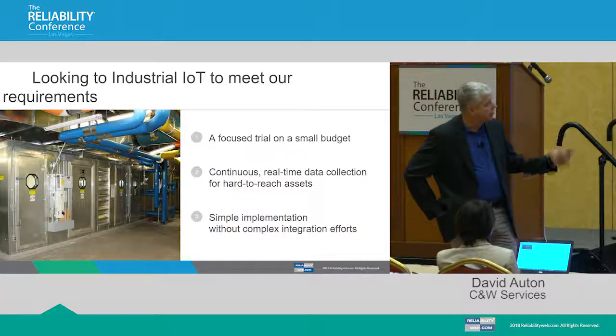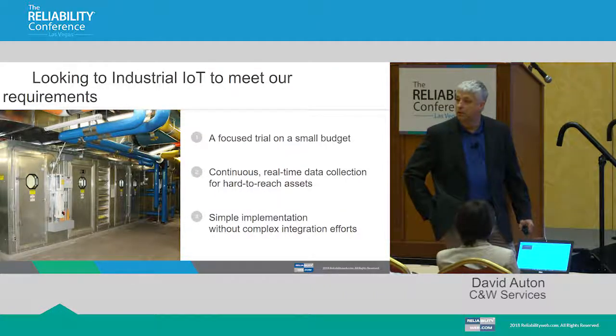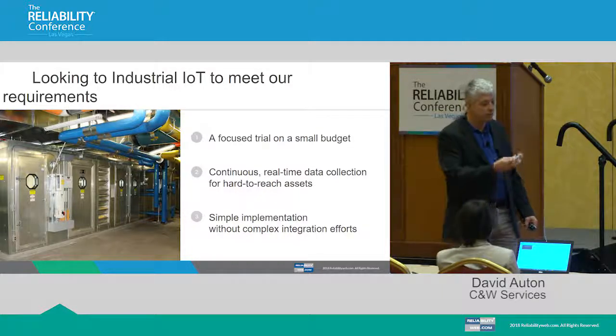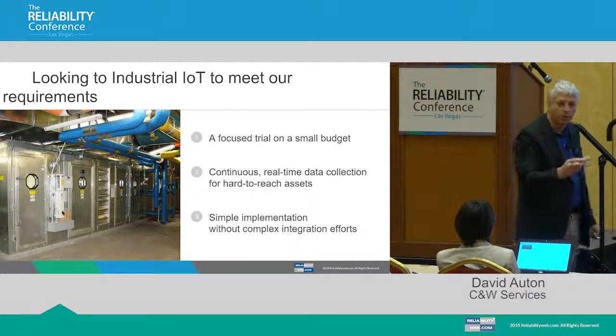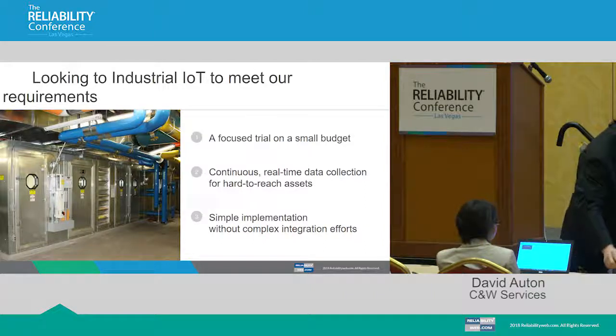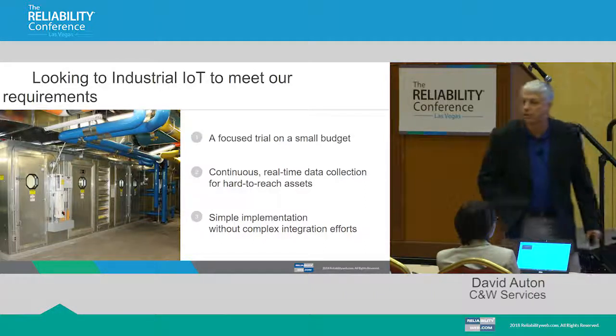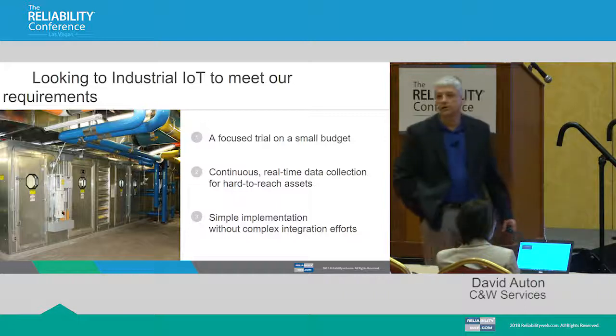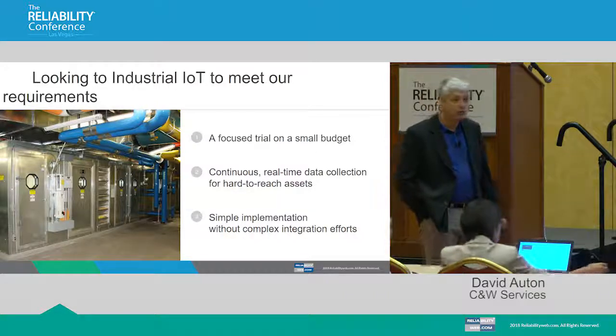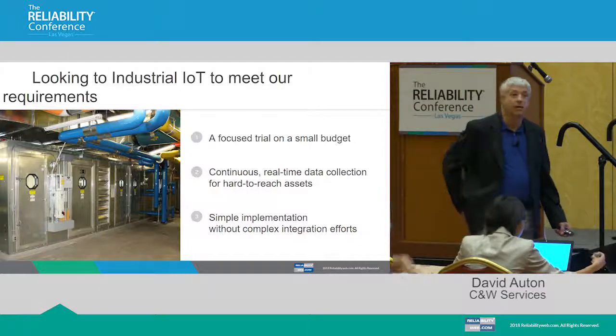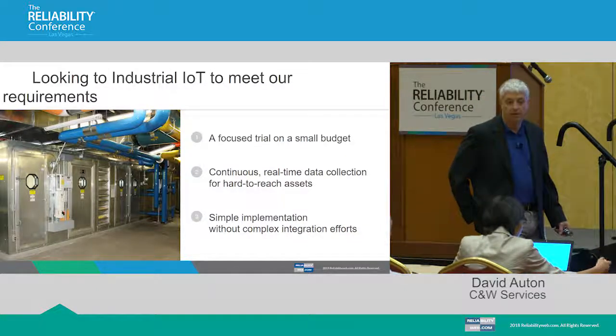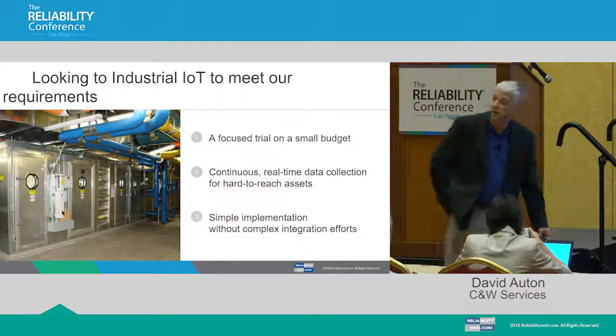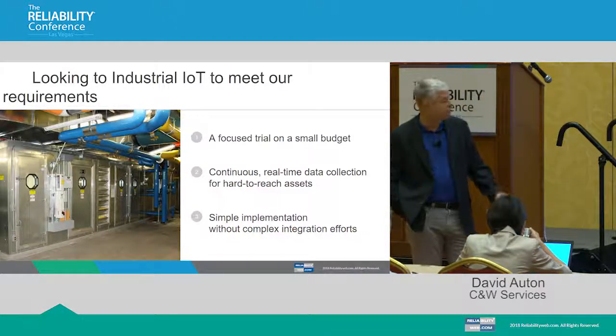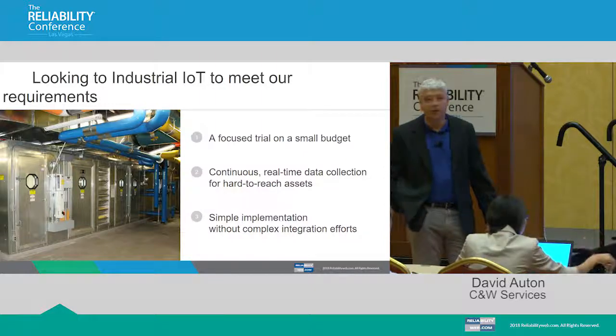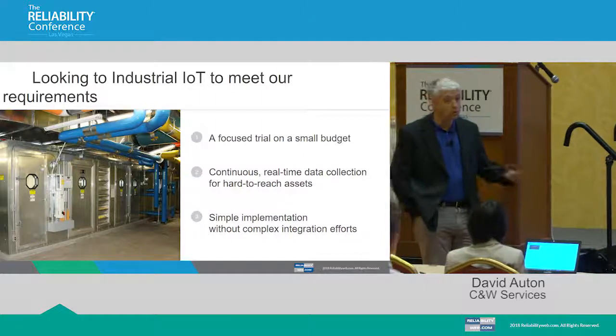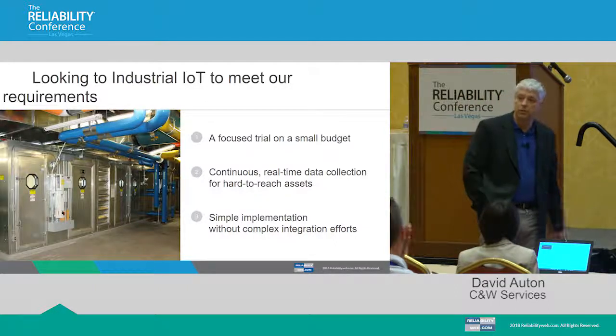And we wanted to get a much higher sample rate. And of course, the new wireless systems, here's the one that we actually used. You can set those up to take samples at whatever frequency you want, once an hour, once every 3 hours, once every 6 hours. And as long as you're doing it once every day or so, it's much better than what we had, right? It depends on how long you want the battery life and how much attention you want to pay to the particular equipment. The advantage, of course, is that you can also increase that. If you're sampling once a day and you're starting to get concerns, or you're trying to do load monitoring, you can set it up to be more frequent.